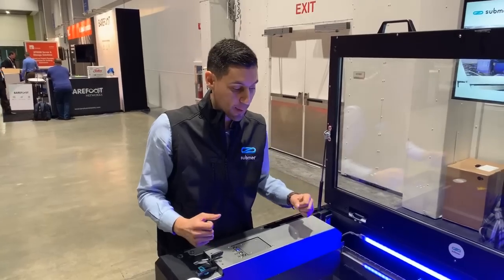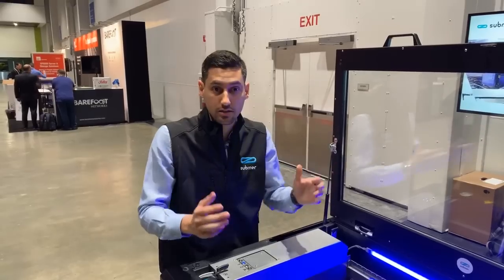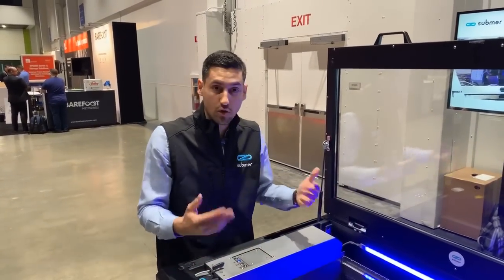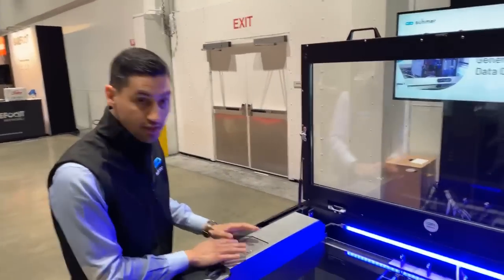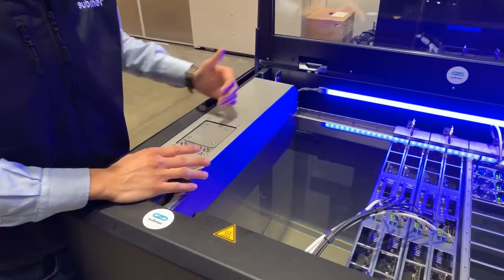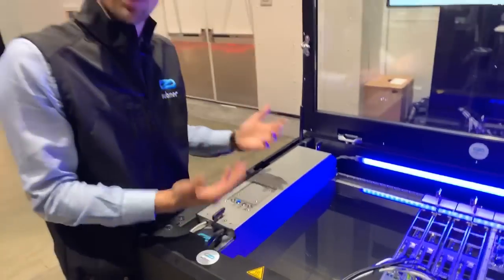Even with the SmartLift, you can also operate it by hand, and you can operate the CDUs like a server. It's the same concept and allows us to automate maintenance of the physical layer of the data center by being able to hot swap CDUs. You don't need to plan ahead the cold aisles, false ceilings, or raised flooring. You just drop boxes, and if you need more cooling power, you just drop more CDUs. We have redundancy installed inside each CDU.